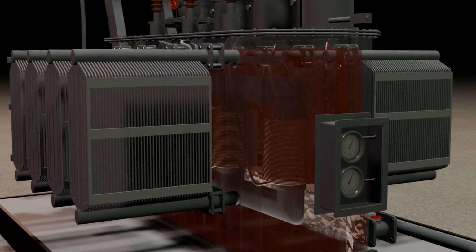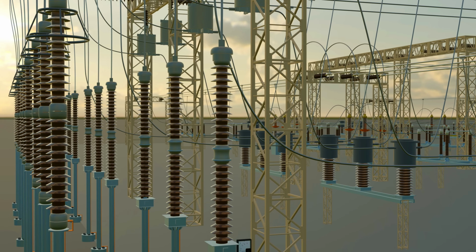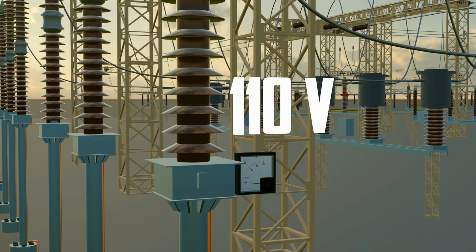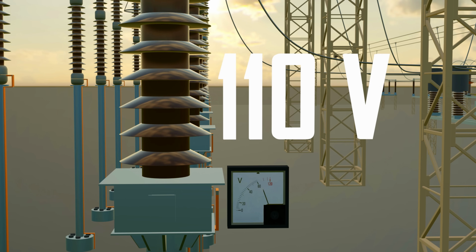Instead of working like a typical power transformer, it uses a capacitive voltage divider with an auxiliary transformer to proportionally reduce the voltage. The reduced signal, usually around 110 volts, can then be safely read by protection relays and metering systems for monitoring and control.